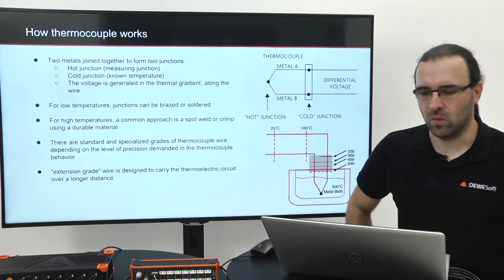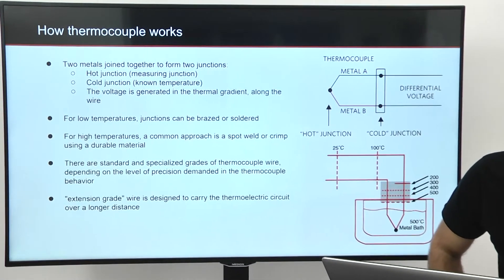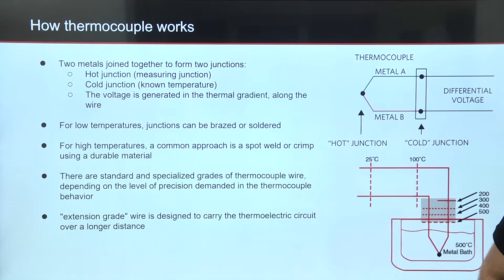When you join two wires with different metals on one end, you get a hot junction measuring junction on one side and a cold junction on the open side. Junctions can be brazed or soldered for low temperature, or spot welded for high temperature measurements. Voltage is then generated in the thermal gradient along the wire.